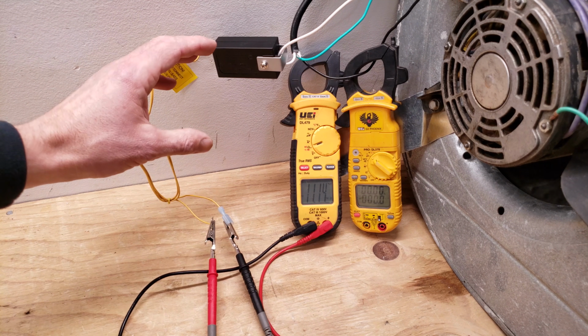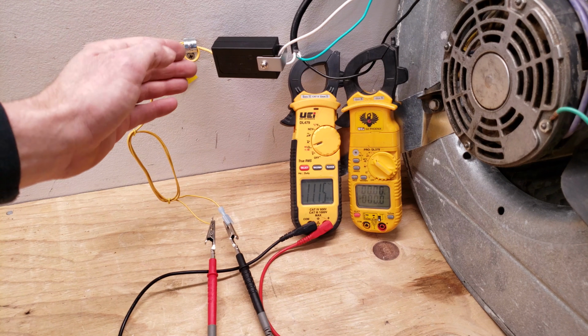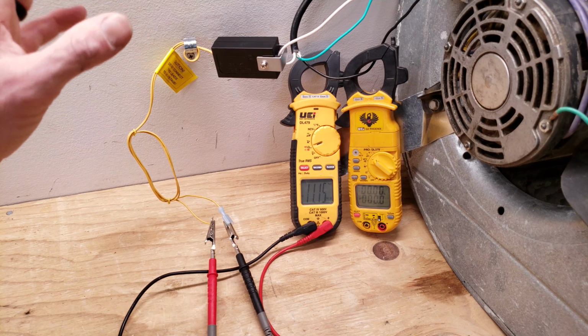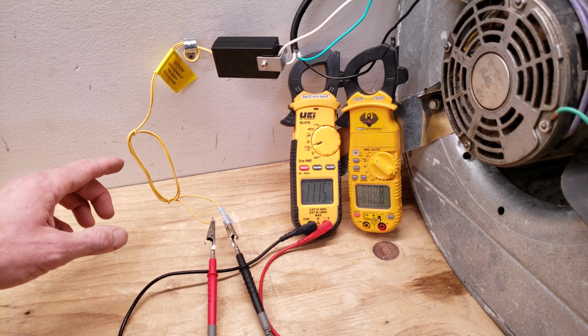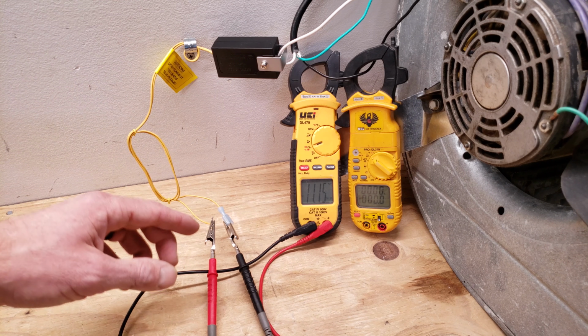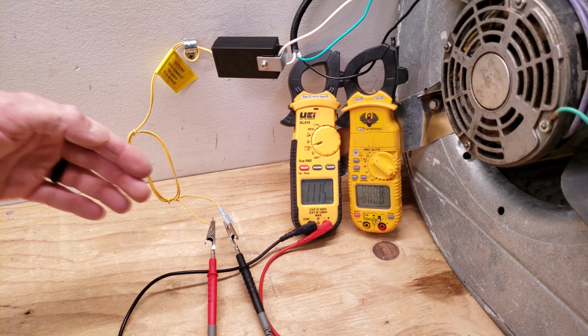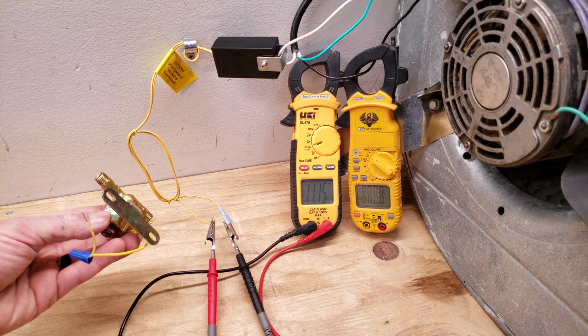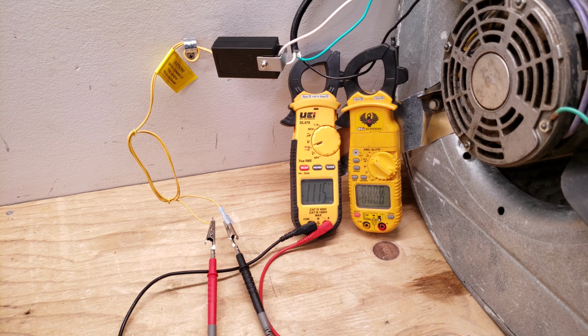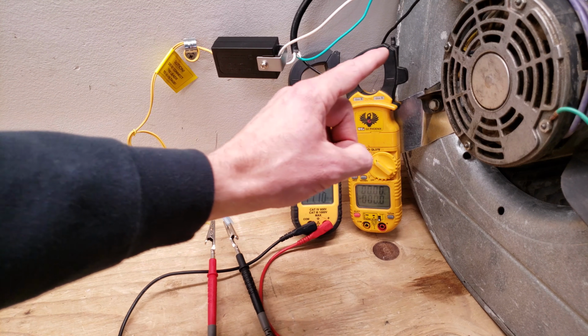So in reference to troubleshooting these, you got to make sure that you have your 24 volts going through that. That's the only way to troubleshoot these, is to see if the 24 volts is making it through over to the load. And in this case, it will be a water solenoid such as this. And the other thing that you need to monitor is the amperage.